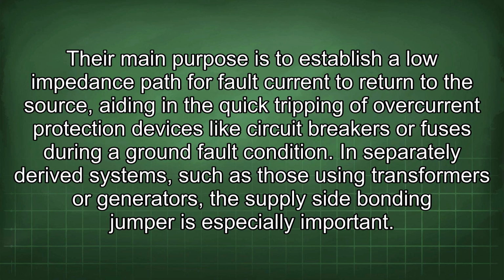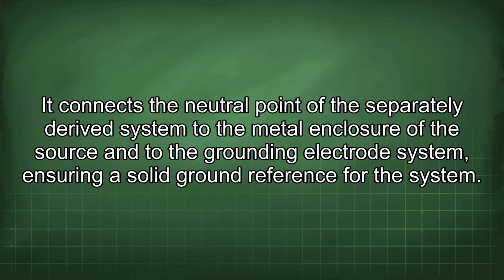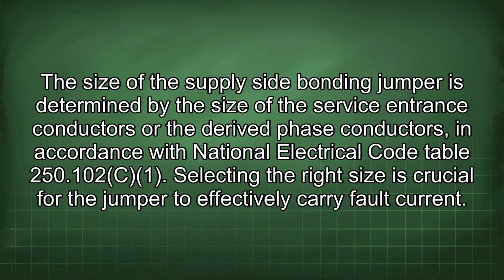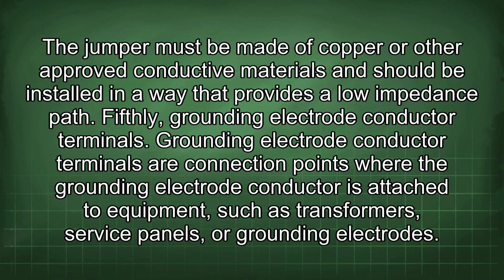In separately derived systems, such as those using transformers or generators, the supply-side bonding jumper is especially important. It connects the neutral point of the separately derived system to the metal enclosure of the source and to the grounding electrode system, ensuring a solid ground reference for the system. The size of the supply-side bonding jumper is determined by the size of the service entrance conductors or the derived phase conductors, in accordance with National Electrical Code Table 250.102. Selecting the right size is crucial for the jumper to effectively carry fault current. The jumper must be made of copper or other approved conductive materials and should be installed in a way that provides a low impedance path.